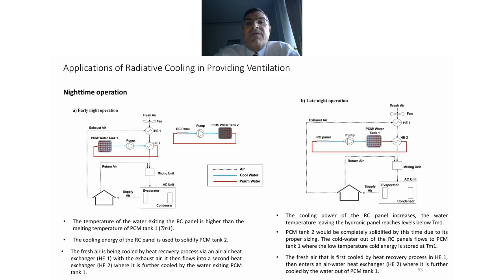So at the same time, the fresh air is being cooled by a heat recovery process, by heat exchanger 1 with the exhaust, and then it's further going over the water for PCM tank 1, and it goes into the room. So the ventilation takes place by 2 things: 1, from the return, the heat recovery, and 2, by PCM 1. And the RC is used to solidify tank 2 to store this cooling inside tank 2.